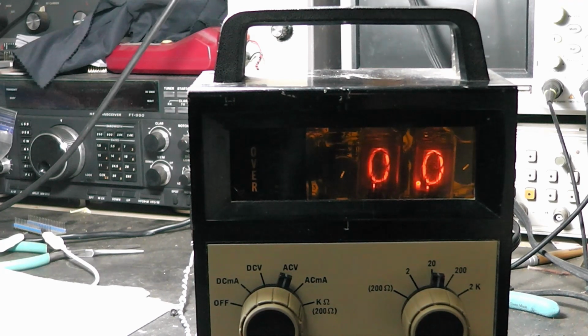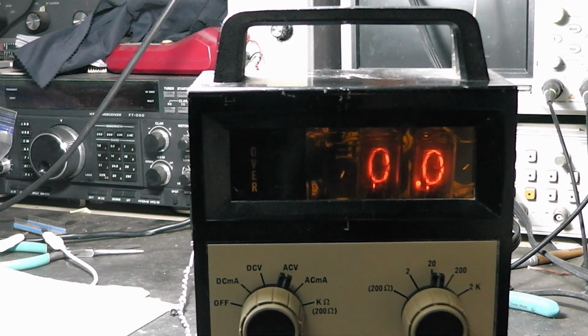Okay, and I think it mentions here somewhere when it settles. Yeah, allow the display to stabilize. And, well, let me back up a minute. Remove it from the AC cal and turn the function switch. Place the probe back on the AC cal test point. Allow the display to stabilize and adjust the AC cal control, which is up here at the top of the unit, for a meter reading of over 00. So we want this to say 00, but over here.